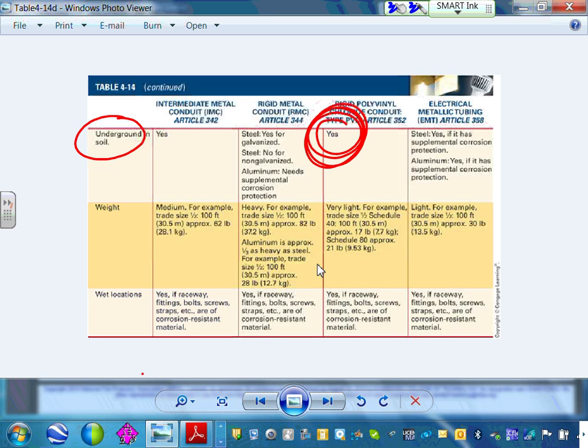Underground in soil, now tell me, which one is your conduit of choice? PVC. Now can you put rigid there? Yes, it has to be treated. Steel, if it's galvanized - steel, not for non-galvanized. Can you put non-galvanized steel in the ground? You can, but you're not going to find it after maybe 5-6 years. You'll find the conductor sitting there and everything else.